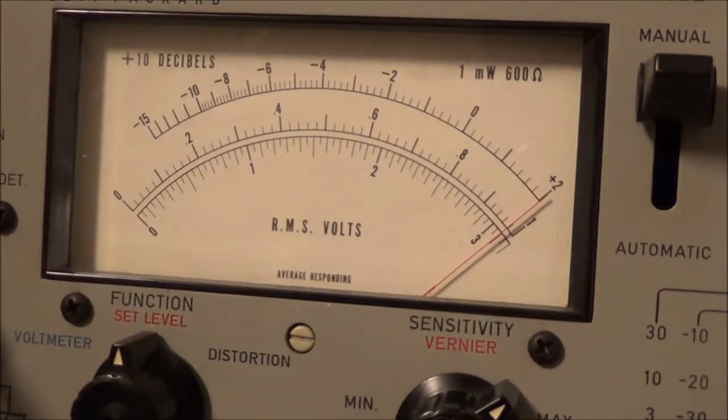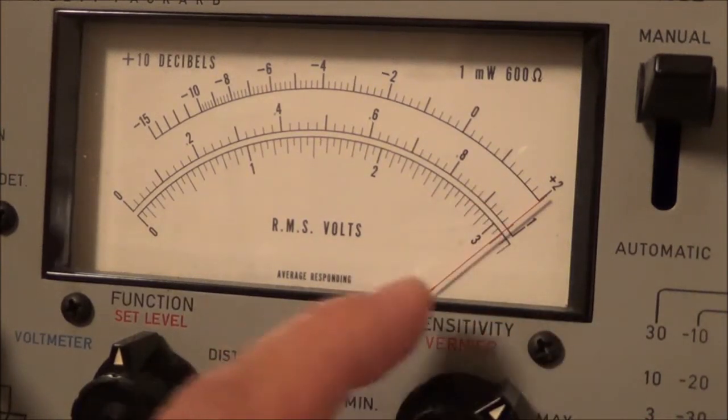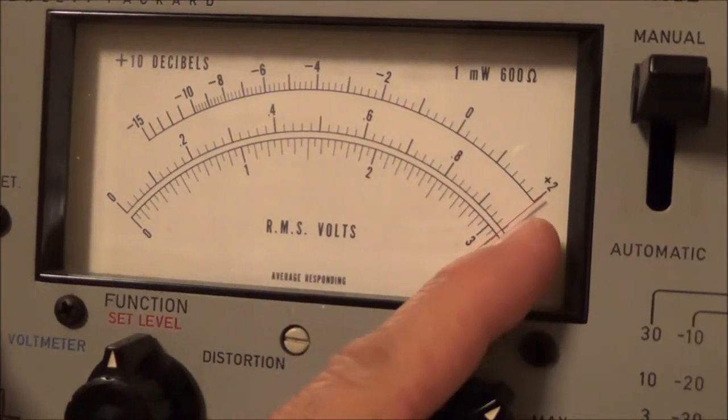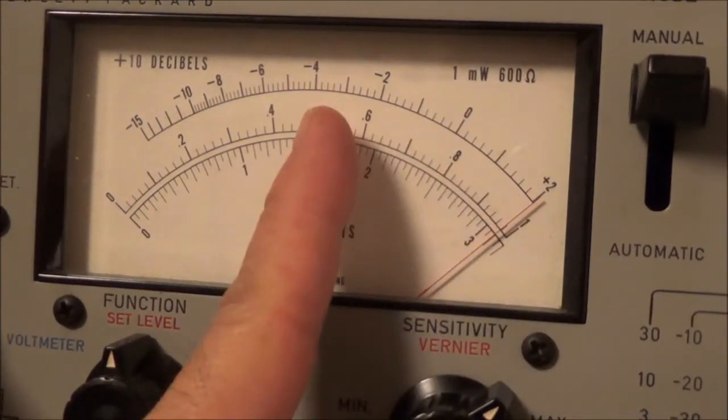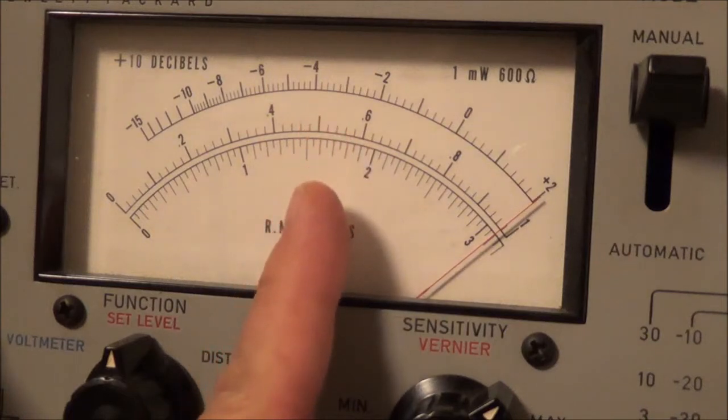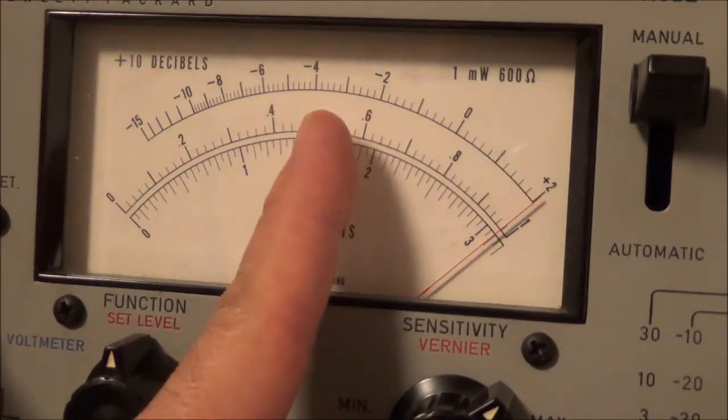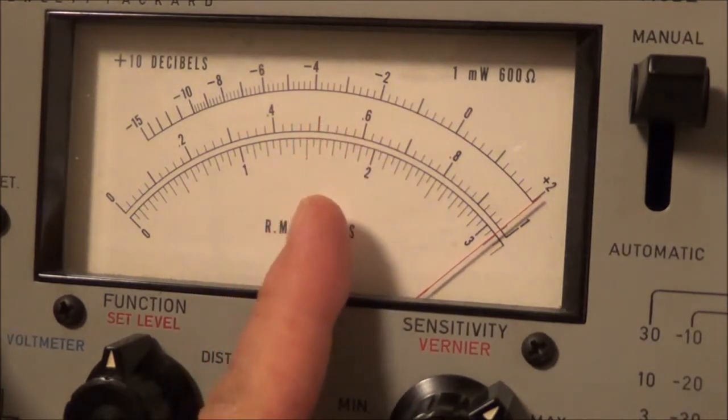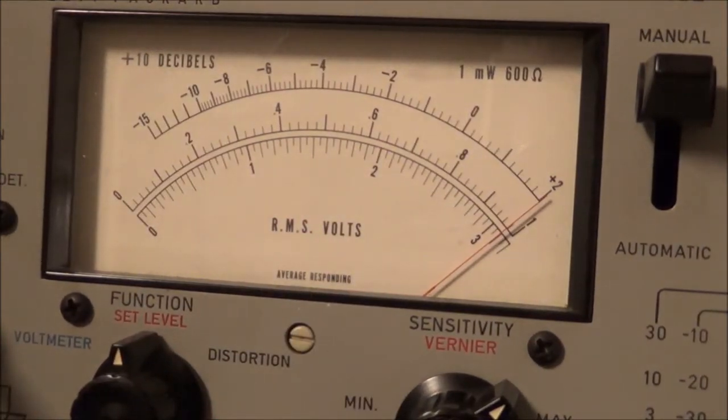So if you can imagine in your mind, part of this being the fundamental frequency and then part of this being the distortion that makes up all of this, the full scale. If we don't set this right here, this vernier, when we're doing the calibration, say we didn't go all the way to here, but instead we went halfway, that certainly would make a difference in your reading. What I think I'm going to try that in a second once I'm done here.